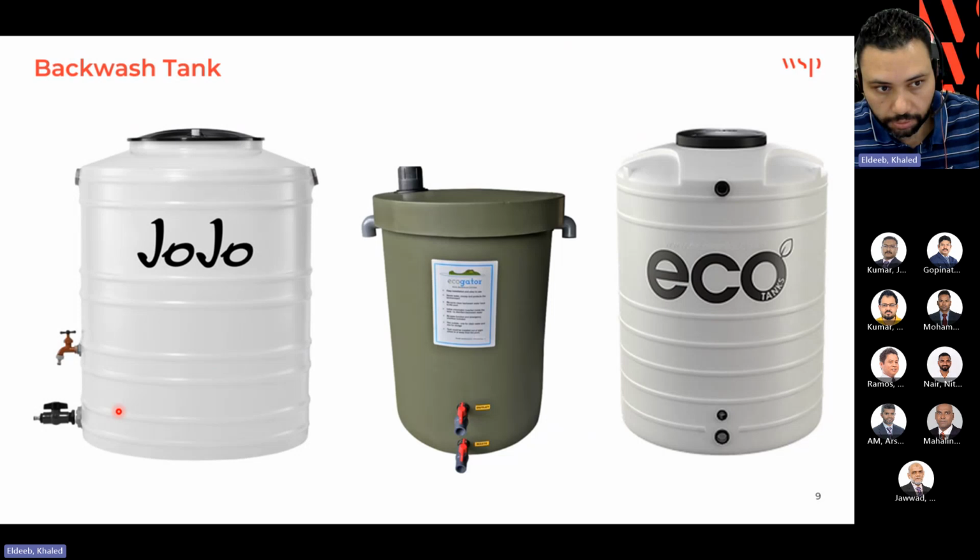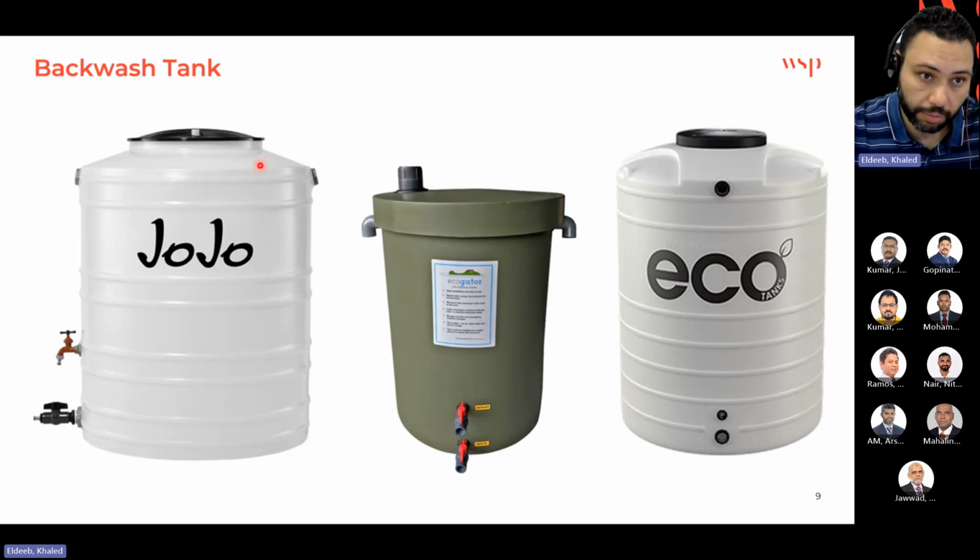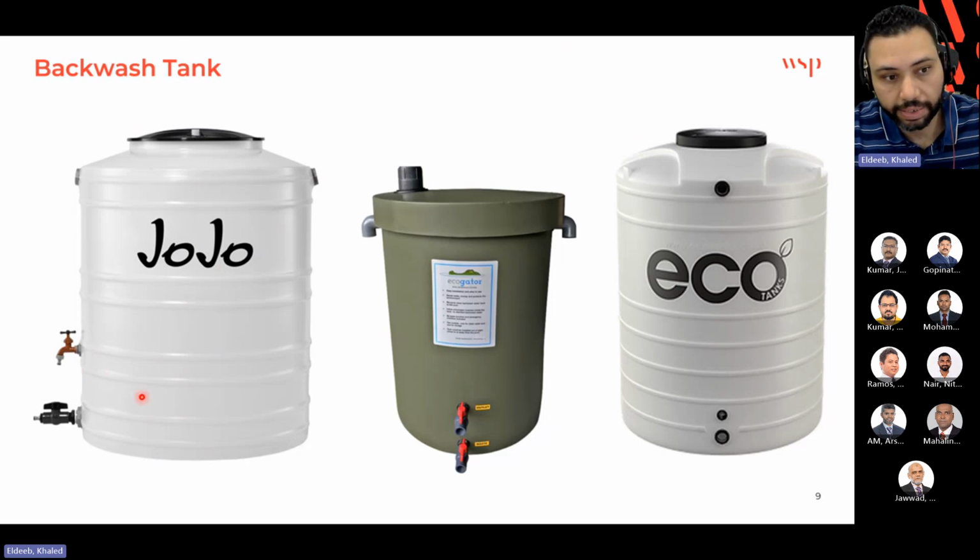Let me explain here. If there is backwash, the backwash comes with dirt and mud or dust, dirty water coming in turbulent flow, and it keeps going here. After finishing, we can keep this water for a long time, maybe half a day or one day. Then the solids like debris will settle down here, and the top portion will be clear, clean water.